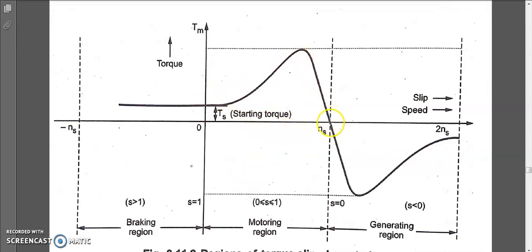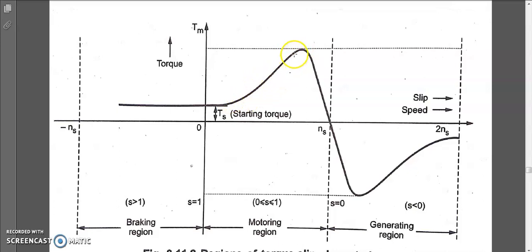During the low slip region of motoring operation, the motor runs almost at synchronous speed. As load increases, slip increases and torque also increases — this is the linear part where torque is proportional to slip. In the unstable region, when operating beyond maximum slip, torque is inversely proportional to s, and the motor will eventually stop, reaching the starting torque point at s equal to one where n equals zero.